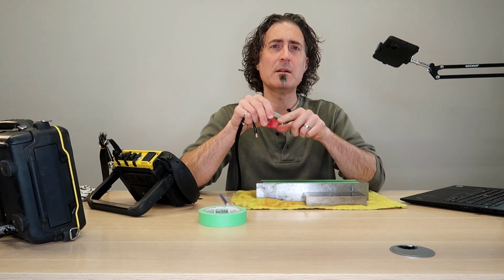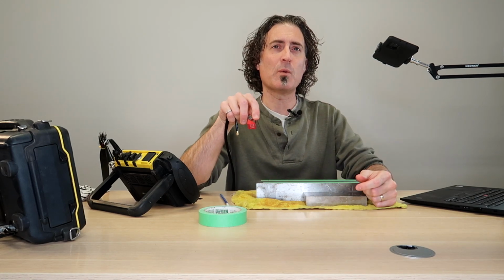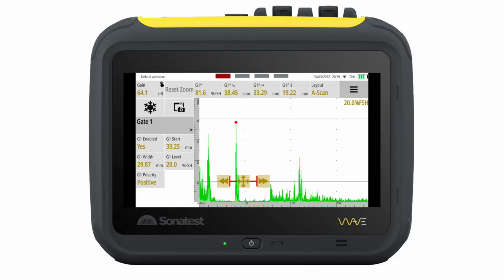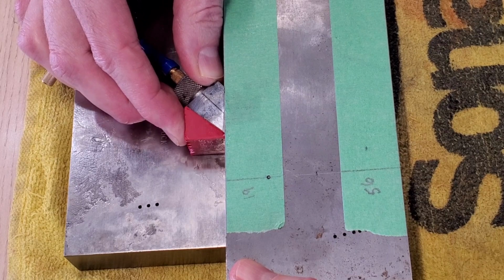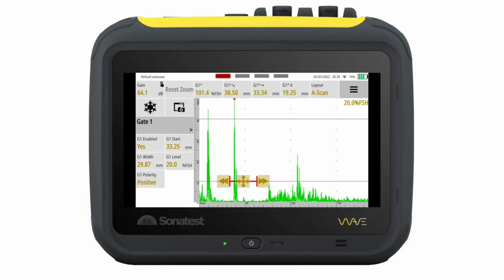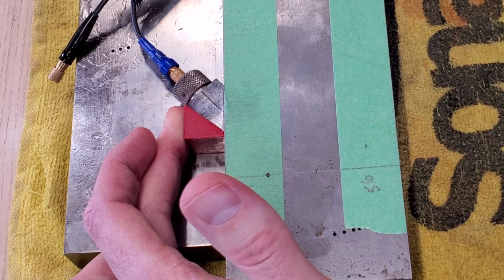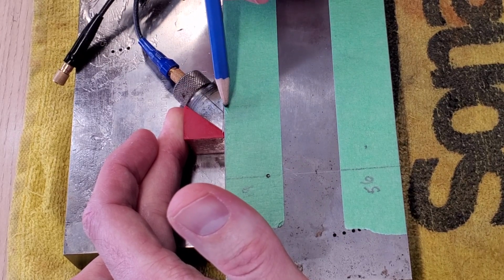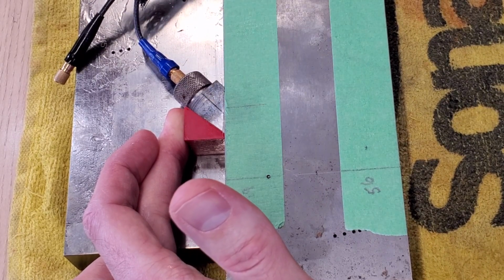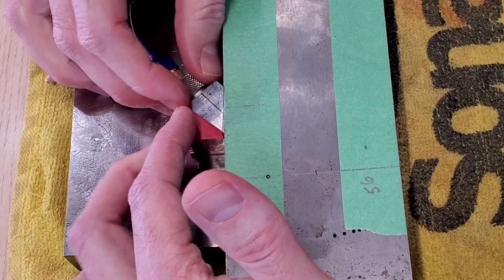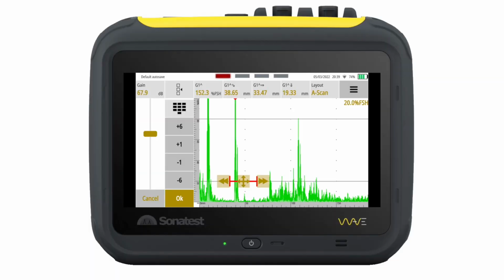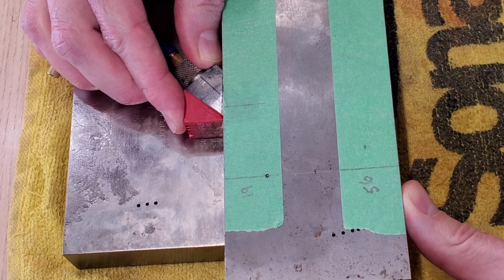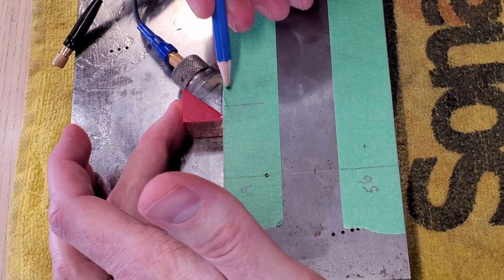And before we get started, we did do a beam index point. It's right in the middle. The first hole is at a depth of 19 millimeters. We're going to move the transducer back and forth until we peak the beam right about there. And then we're going to mark the center of the beam right here with a long line. Then what I'm going to do is add 6 dB, pull the transducer back until that signal comes back down to my reference line right here. Again, mark the position of that line.